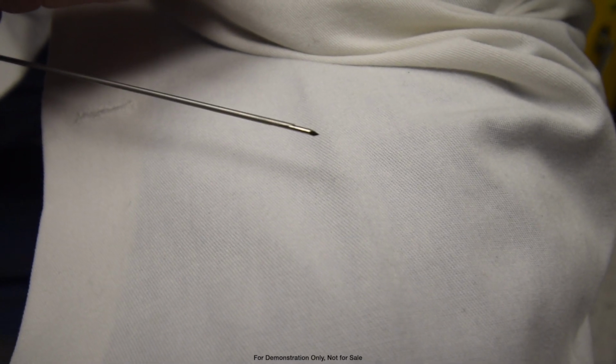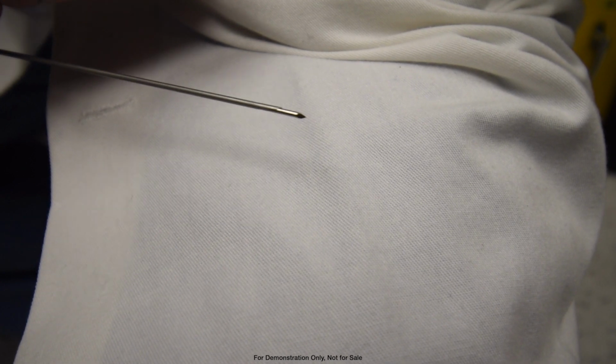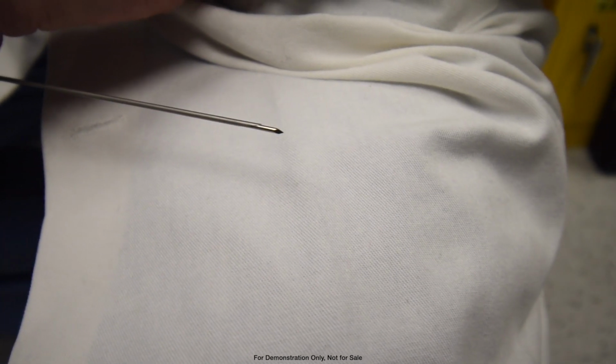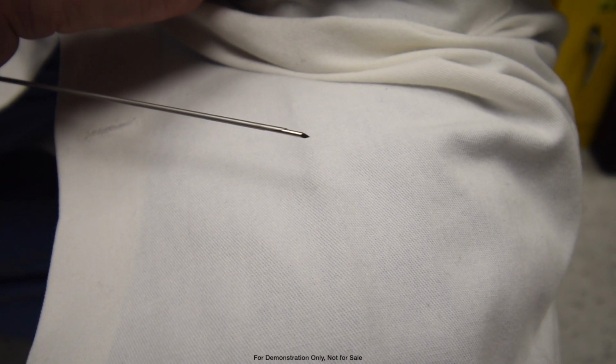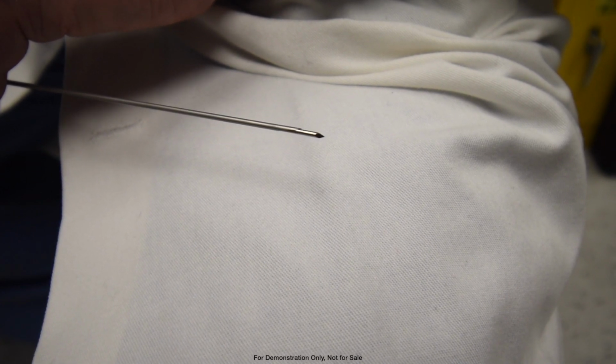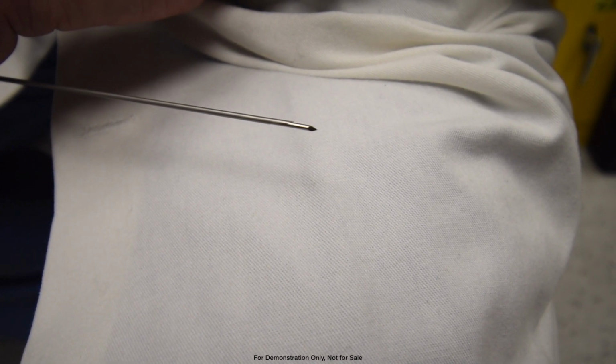The first challenge was to develop a needle that would not deflect. So we designed this trocar tip, and when we tested in the lab, comparing it to other needles commonly used for biopsies, we found that this needle deflects 1/9, or an average of 0.1 millimeters when fired into a hydrogel.